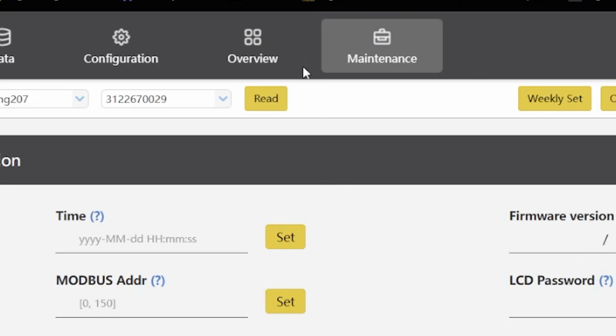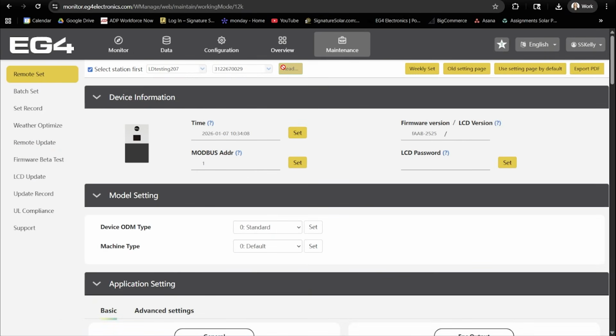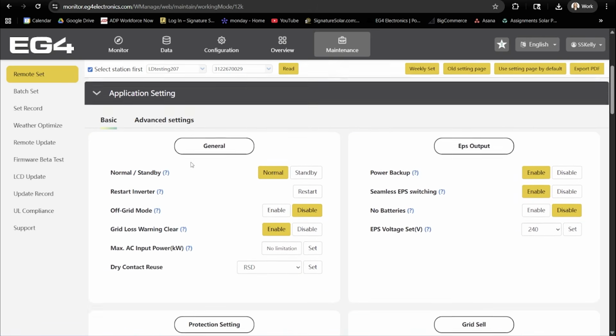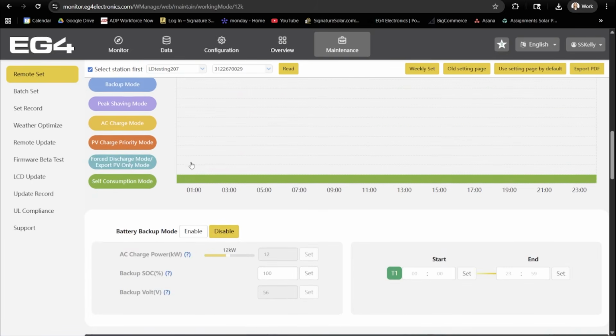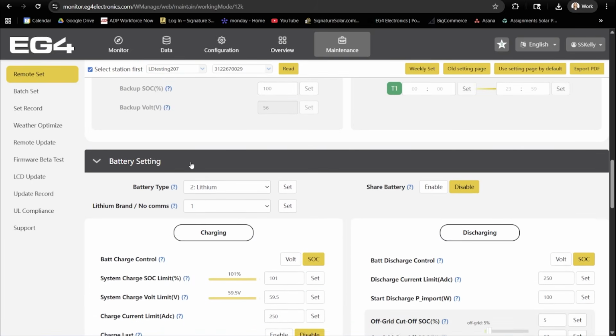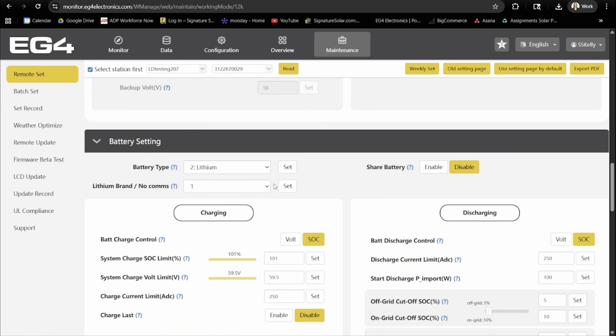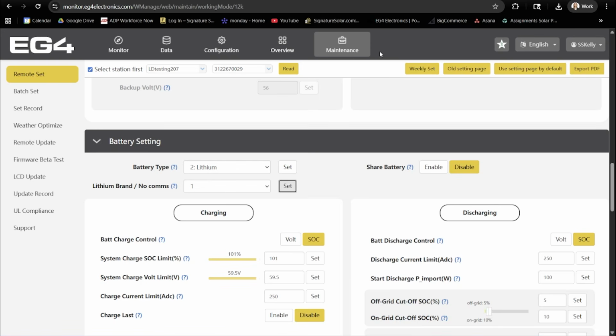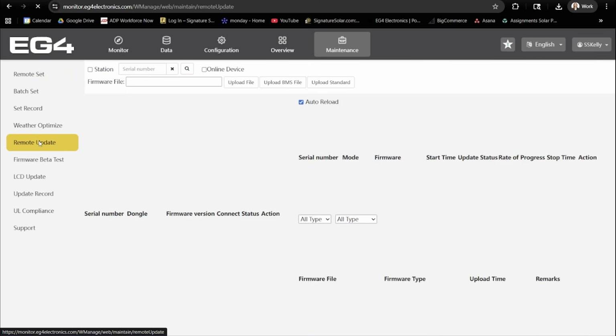Next, navigate to the Maintenance tab and click Read. Once the system parameters finish loading, open the Remote Set menu. Here, confirm that the lithium brand is set to lithium 1. If this setting is not correct, stop and correct it before proceeding. This is an important configuration check before running the OTA update. If you do need to make a change, be sure to click the Set button next to the setting so it is properly saved. If battery details are still not populating at this point, stop and verify that you are using a compatible EG4 hybrid inverter and that both the inverter firmware and the Wi-Fi dongle are fully up to date before continuing. Next, select Remote Update.